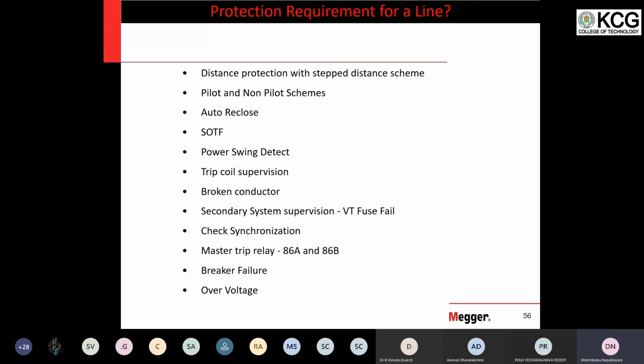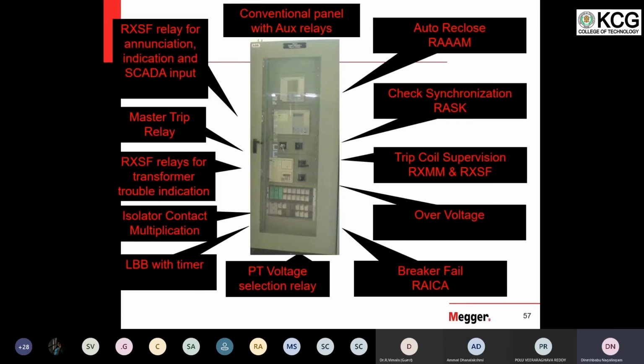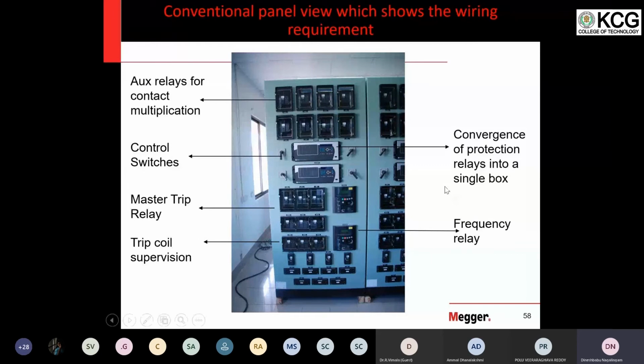So normally for a distance protection, we need distance, pilot aided, non-pilot aided, auto recloser, SOTF, power swing, trip circuit supervision, broken conductor. So, to name a few, we have written this. Each one is a different relay, relay 1, relay 2, relay 3, relay 4, etc. So in a panel, we will have several relays. But nowadays, you can see here, this is numerical relay. So many relays are there, electromechanical relays.